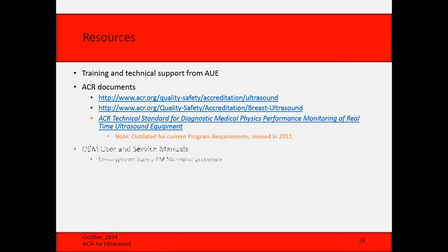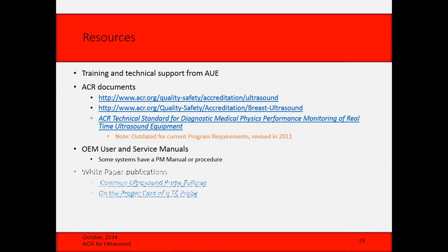reference document. The manufacturer's users and service manuals may have a PM manual. They may also have a PM manual separate, by the way. Some companies do that. And it may have a procedure that you can follow, and very often they'll have one that tells you how to test all the buttons, and that's one of the things that we should be doing on PMs regularly too, in my opinion. There are some white paper publications out there you can get that tell you how to inspect probes: one on ultrasound probe failures, and another on the proper care of a TE probe.